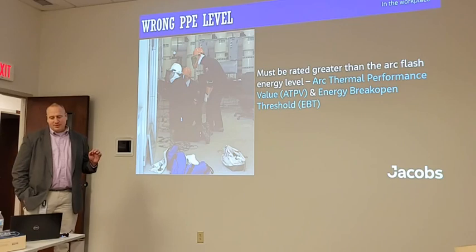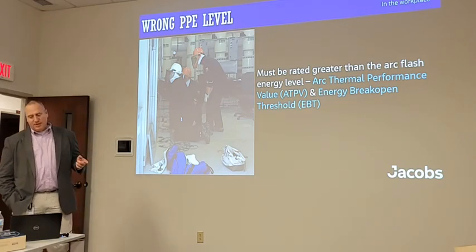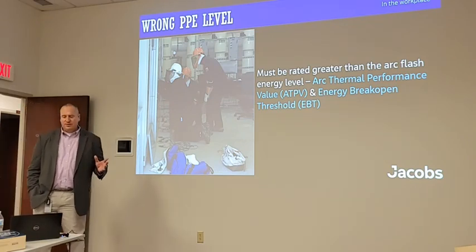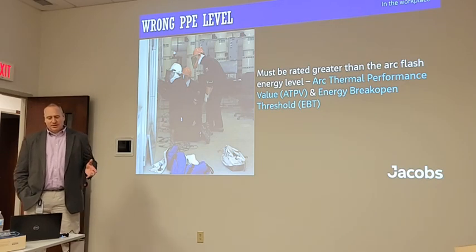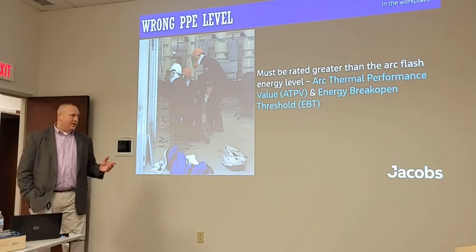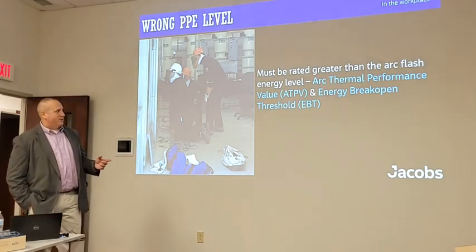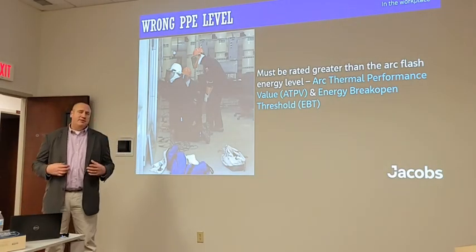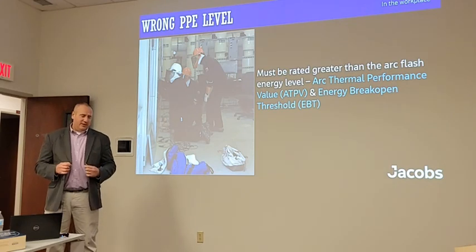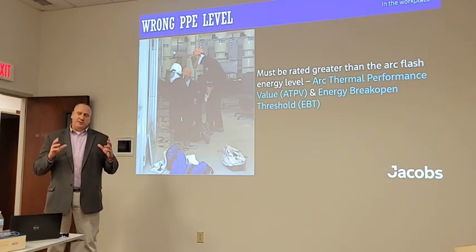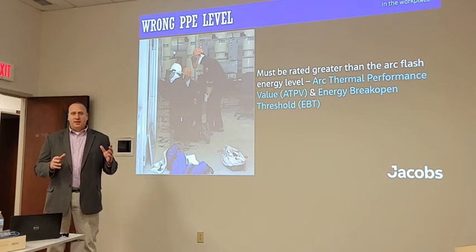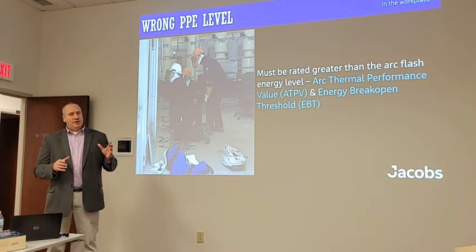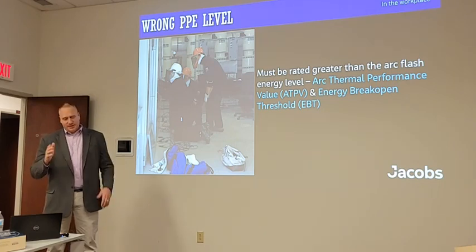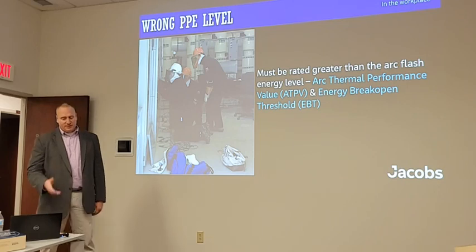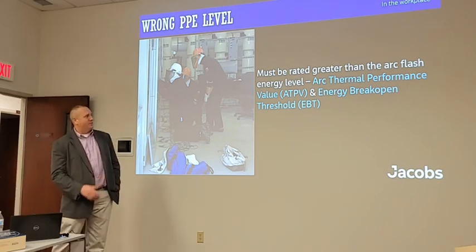And there's two ways that they rate them, either the arc thermal performance value or protection value. I see both of those terms, the ATPV, or the energy break open threshold. And this is how they test garments. The arc thermal performance value is the material. They take a cloth, whatever they're going to make the garment out of, and they'll expose it to different levels of arc flash energies. And at the point that it starts to burn or melt or show signs of degradation, that's the maximum level that it can be exposed to. So it's when it starts to burn or break down the material, that's the performance value.